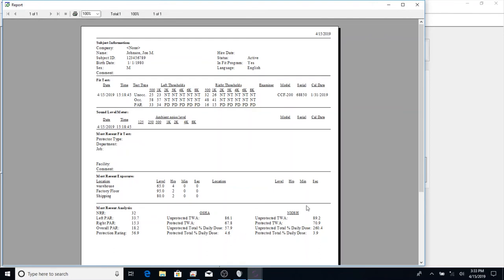For NIOSH, however, unprotected, he's getting 260% of his daily dose of noise, which is an issue. However, when he has his hearing protection in, he's within safe levels.